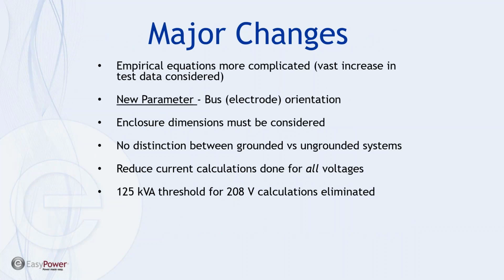The major changes involve the empirical equations, where we used to have 4 equations. Now there's something like 10, and they have to be reiterated multiple times in the calculations, and then correction parameters and adjustments are made based upon the individual system. The enclosure dimensions must be considered, especially if they're non-standard or non-typical for the voltage or the equipment involved. We'll touch on that briefly. There does not seem to be any difference between a grounded and ungrounded system, as we used to verify. And reduced current calculations are done for all voltages. We'll talk more about this when we get into the analysis presentation. And we talked also about how the low voltage exception has been eliminated.